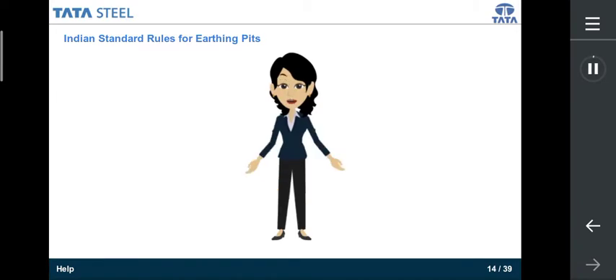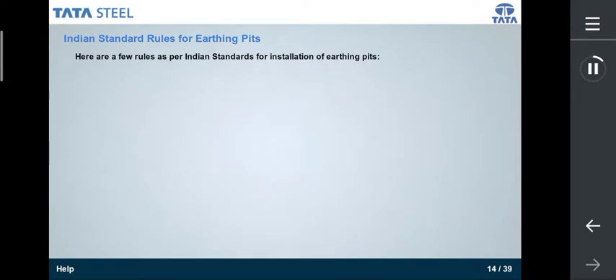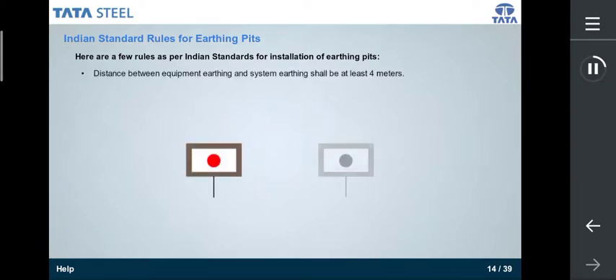We have discussed so many things about earthing. But have you ever thought who governs and specifies the rules or standards? Yes, all these earthing related specifications are done as per Indian standards. There are quite a few set standards that need to be followed regarding installation of earthing pits. Let us take a look at them. Distance between equipment earthing pit and system earthing pit shall be at least 4 meters.